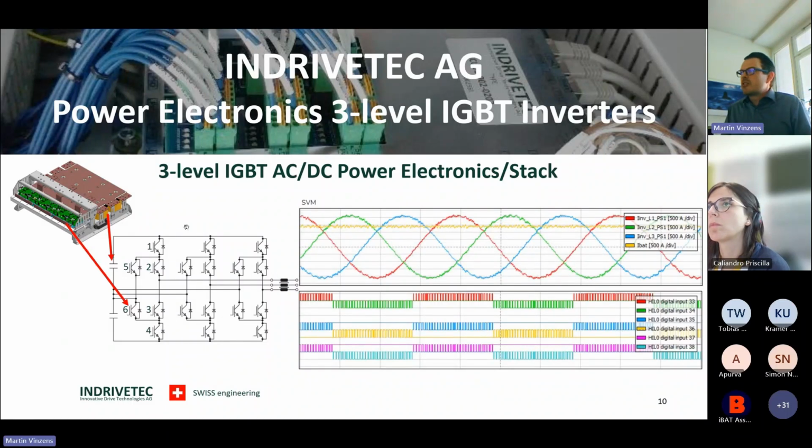So with this technology, you can achieve higher voltages as well with this ANPC active neutral point clamping technology. You can modulate instead of like shown before with a full 1000-volt DC voltage turn on and off. You can have now steps, so you can do 750 volt or 1500 volt, and you can build up, let's say, make smaller steps and blocks.